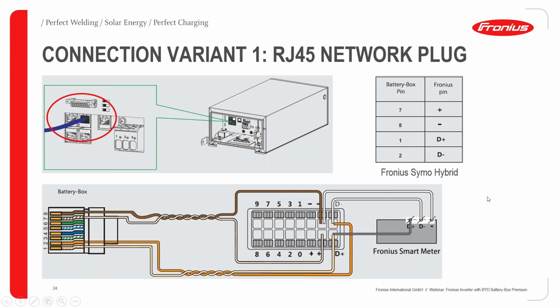So essentially four wires for your comms there, and these are the pinouts. Depending on where the battery is, you may have it in the middle point or the end point, but like any RS485 connection, the two endpoints need to have the 120 ohm resistor activated. In the case of our smart meter, that's a physical resistor you connect if you're used to mounting smart meters. At the battery end, it's the dip switches - so the midpoint, which is your data manager from the inverter in this case, would be switched off. I've got some slides to show that as well.